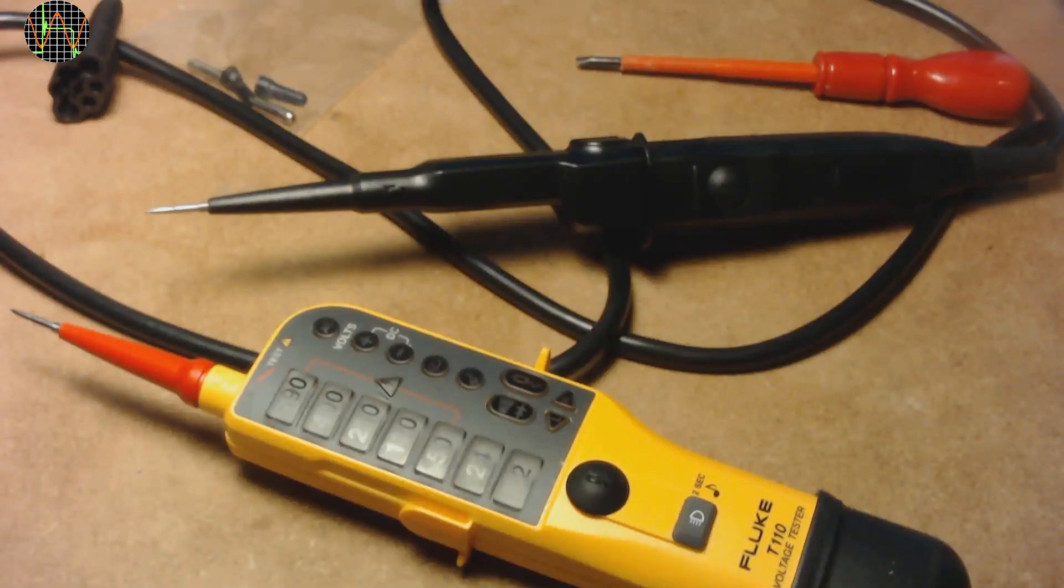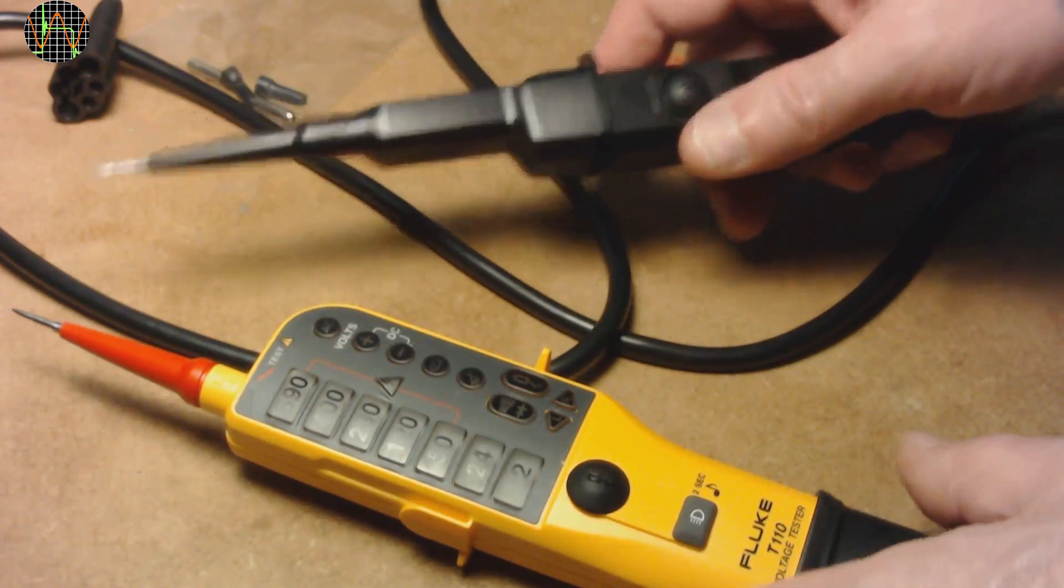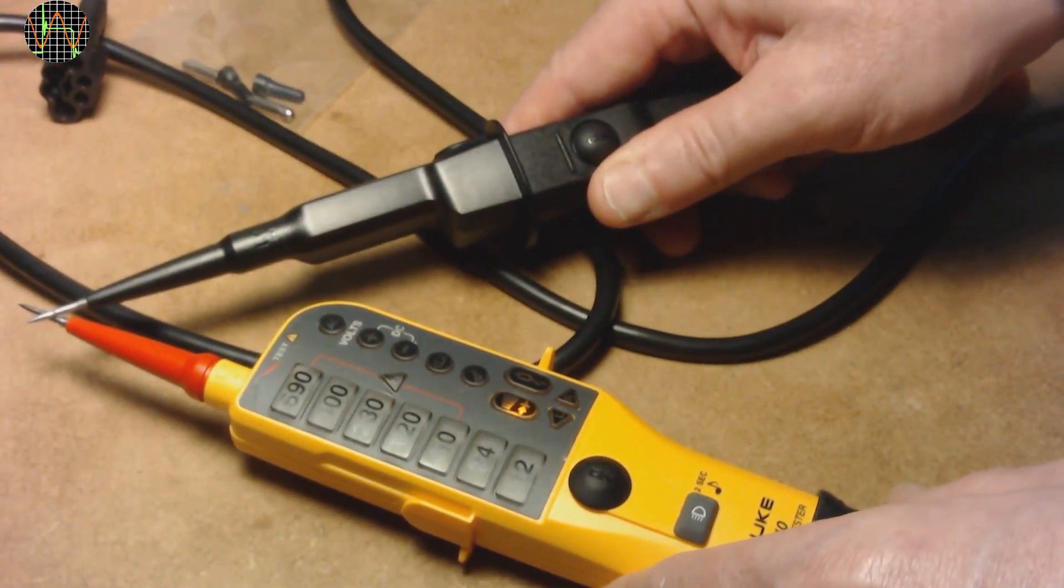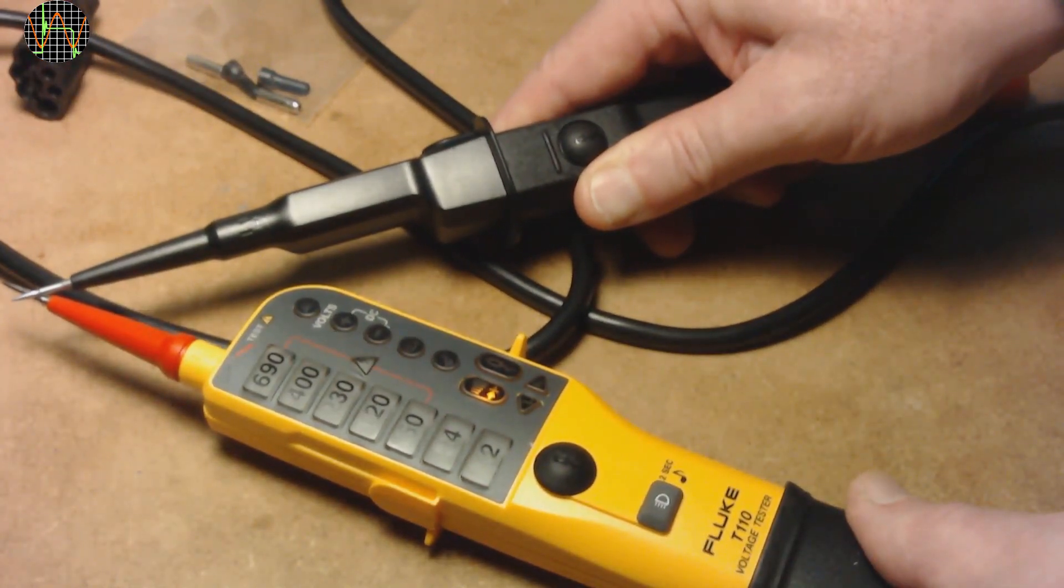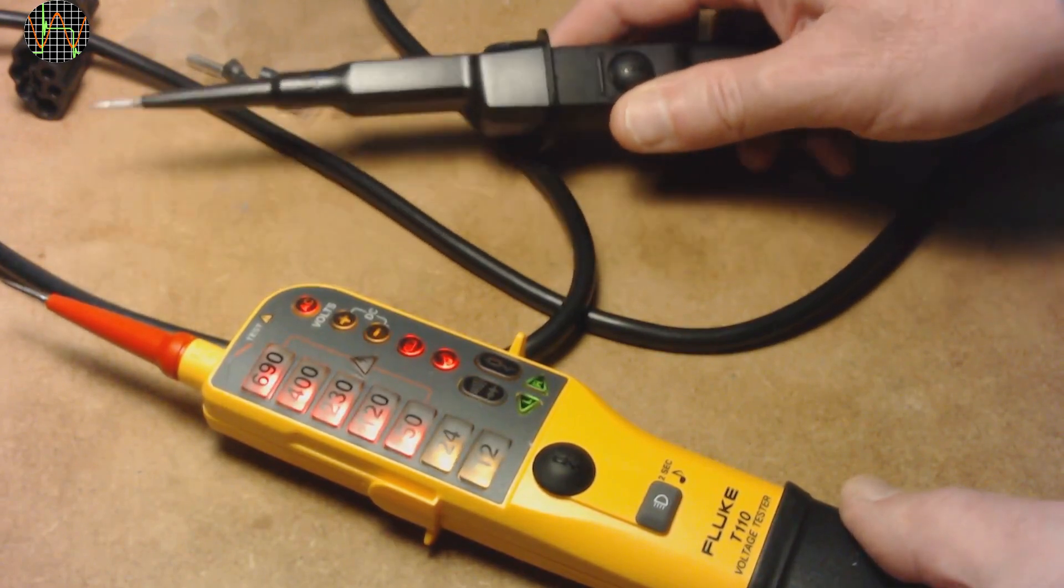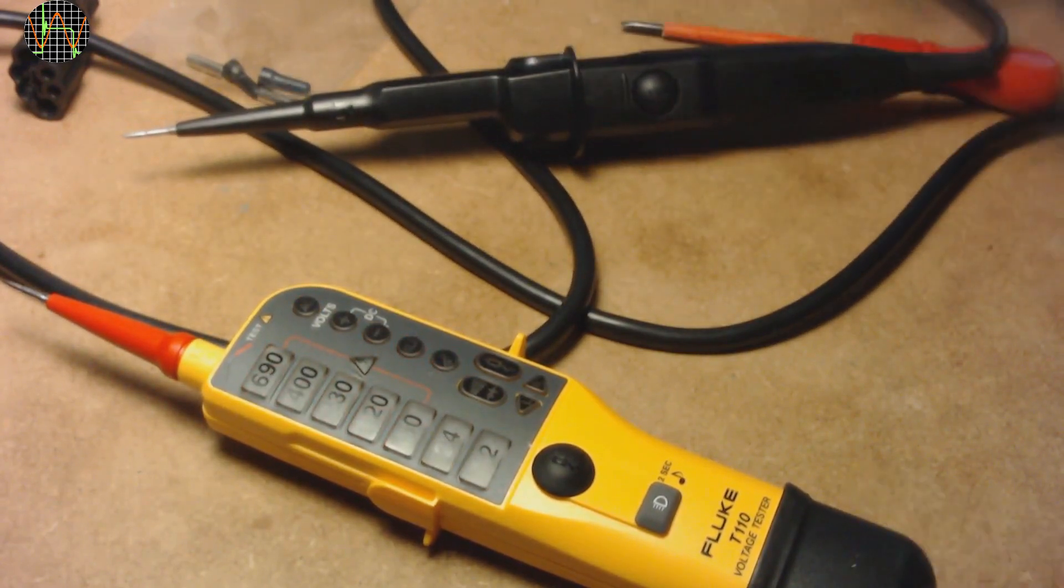The manual states that one is supposed to carry out a self-test before using the unit, and that the unit is not supposed to be used if the self-test fails. To do a self-test, you need to hold the probes together like for a continuity test, but for more than 3 seconds. Then all lights except two should come on briefly.